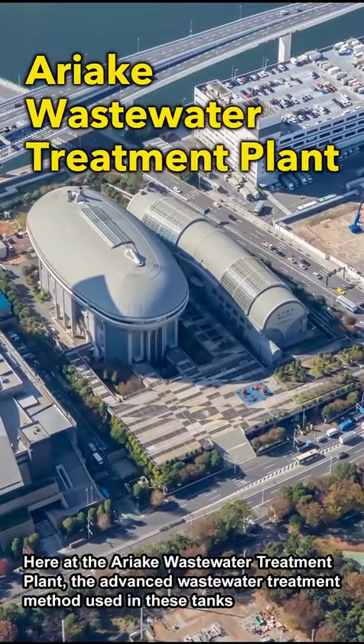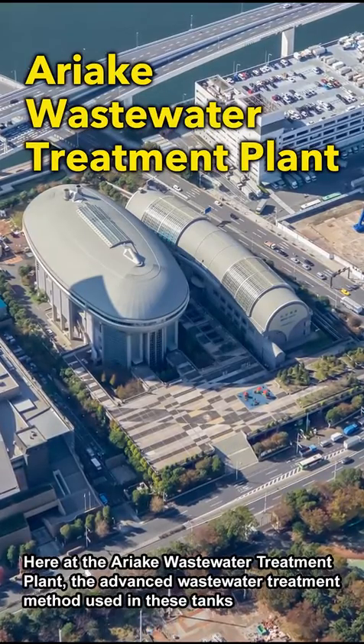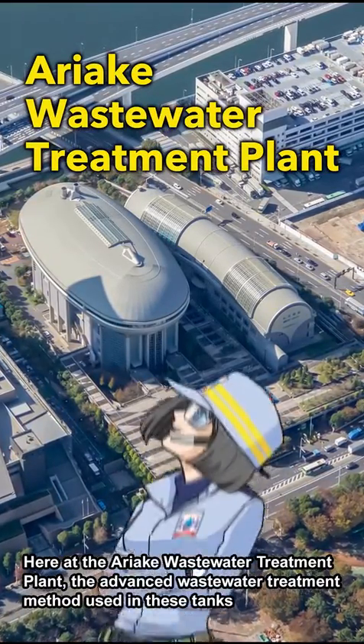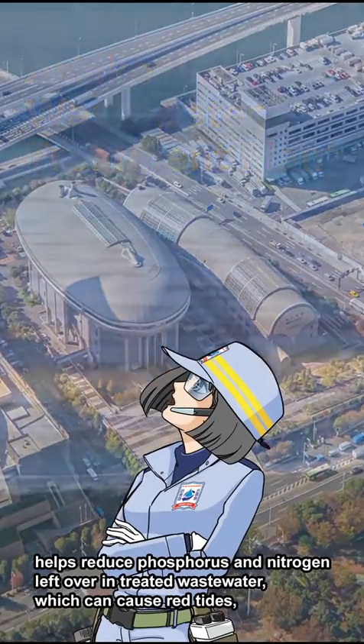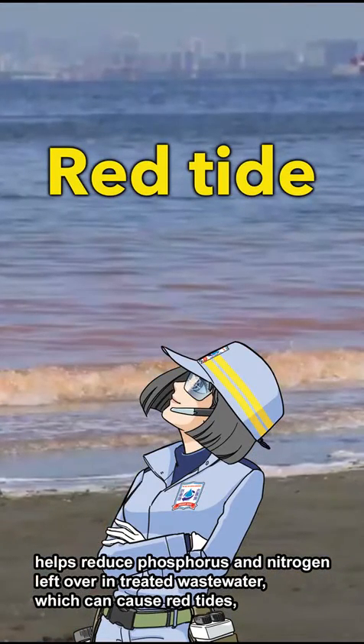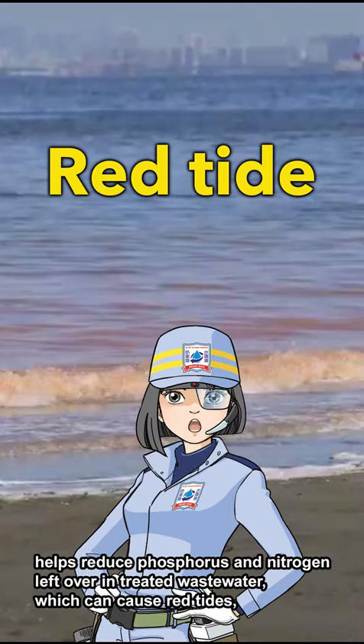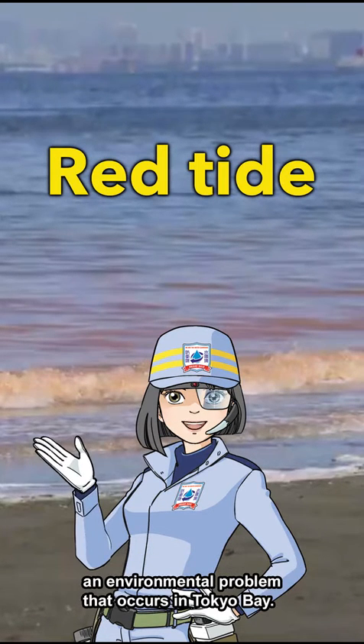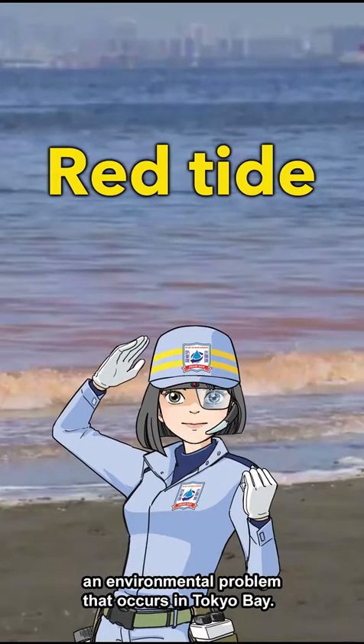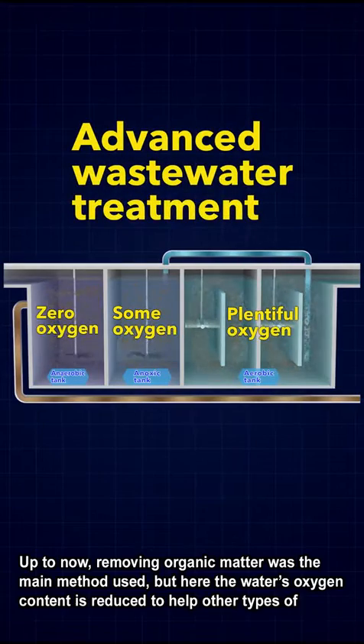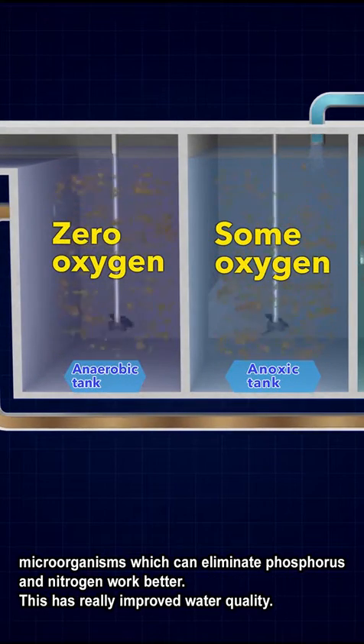Here at the Ariake wastewater treatment plant, the advanced wastewater treatment method used in these tanks helps reduce phosphorus and nitrogen left over in treated wastewater, which can cause red tides, an environmental problem that occurs in Tokyo Bay. Up to now, removing organic matter was the main method used, but here the water's oxygen content is reduced to help other types of microorganisms which can eliminate phosphorus and nitrogen work better. This has really improved water quality.